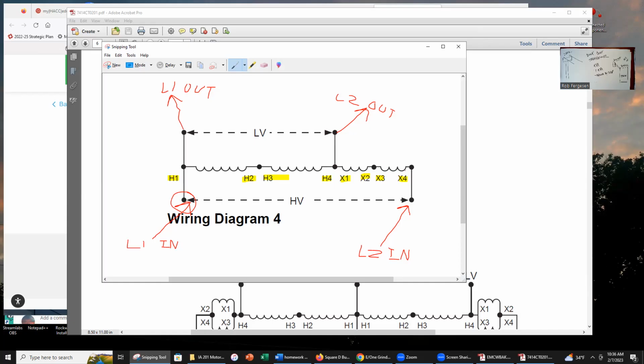But then from a wiring perspective, I'm going to take a wire nut and attach H1 to L1 out and L1 in. So all three of these are going to be wire nutted together, 3 wires wire nutted together. The other thing I'm going to do is have L2 in attached to X4. So that's going to be wire nutted together, just 2 wires. And I'm going to take H4 and X1 and attach that to L2 out. So those are 3 wires wire nutted together. And those are my inputs and my outputs to the transformer.